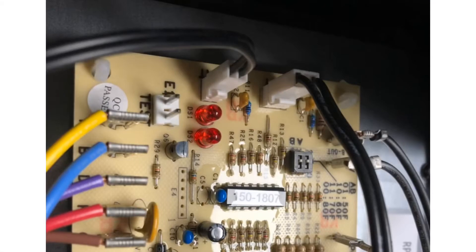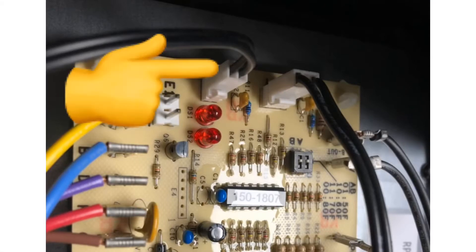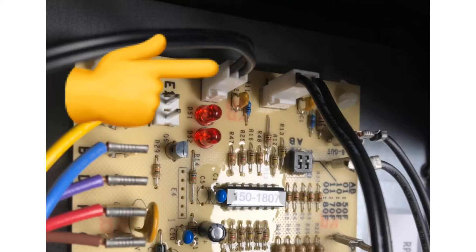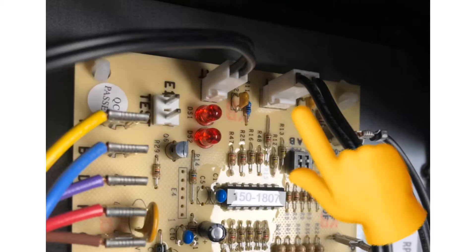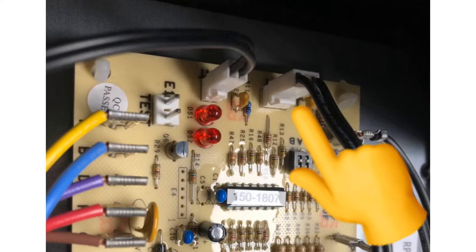All right, let's take a look at our sensors here. The one here to the top left, that's going to be our outdoor ambient temperature sensor. That's the one that's going to hang down on the outdoor unit. And the one to the top right, that's going to be our coil sensor. Both of these are two-wire thermistors, but the coil thermistor is a three-pin plug, but the middle pin is a dummy pin. That's so we get them plugged in the right place.